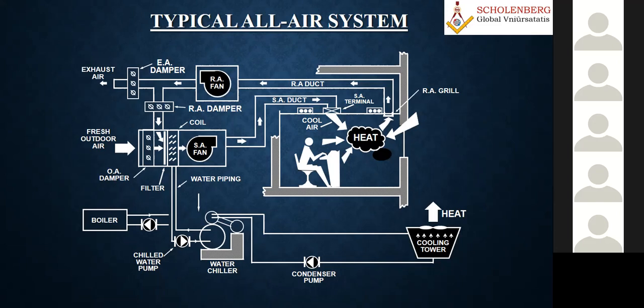Again, what Dr. Ramaswamy is saying is that it depends on application to application. For example, suppose there's smoke inside the room. What you can do is simply shut this return air damper, and this return air fan acts as the exhaust. So all the smoke in the room can go outside, and fresh air can be introduced. Now let's take the other case, for example marine and offshore applications. In these applications, suppose a fire breaks out, and suppose this particular room is a telecom room, then the air gets recirculated in the room. So the exhaust air damper here gets closed, the fresh air damper here gets closed, and only the return air damper gets opened, and air gets recirculated within the room just to have the cooling inside. So again, it depends on application to application.